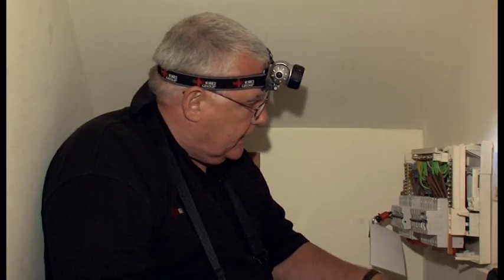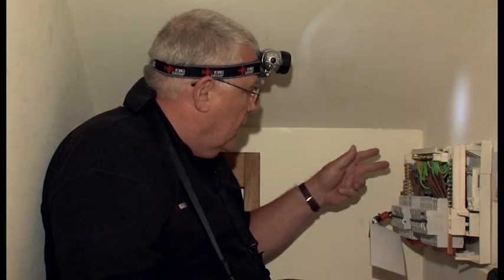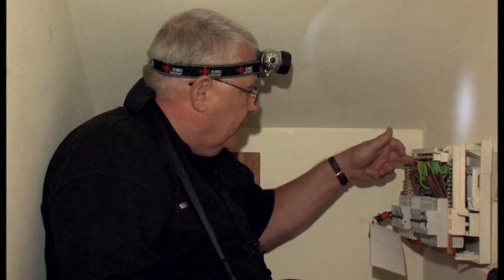Harsh. So I've now confirmed that we have an earth. We have a value of Ze and also the value of prospective fault current. In this case, it was prospective short circuit current between line and neutral which was higher and will be noted as our PFC. However, I wouldn't have been surprised if they'd actually been about the same, because behind here is the PEN conductor and I've only got about a metre of tails here, so there's only a difference between 25mm and 16mm for a metre, so they could well have been the same.